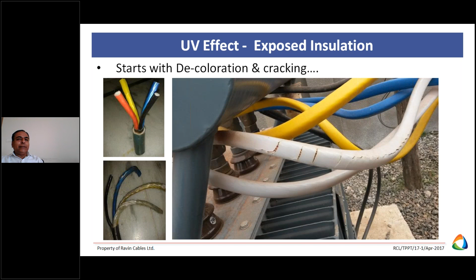You find some cracking at the ends of the cable or termination side. In XLPE cable, once exposed directly to sunlight, it gets cracked. This cracking phenomenon happens in XLPE cables but not in PVC cable. We can avoid it by putting adhesive black tape over it, so there's no effect of the cracking. The biggest drawback, which nobody talks about, is that in the event of fire, XLPE burns like a candle, while PVC is self-extinguishing.